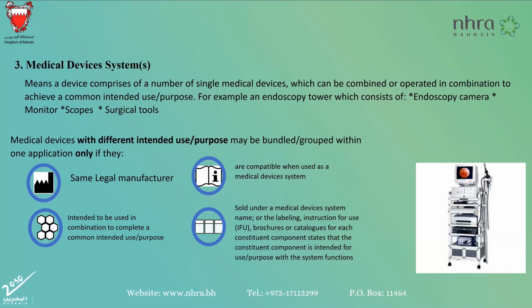But these components, when they are combined together, achieve a common intended use or purpose. So in that case, they can be bundled together using this bundling group, if they are under the same legal manufacturer and under one medical device system name and sold as one package, not each device separately.